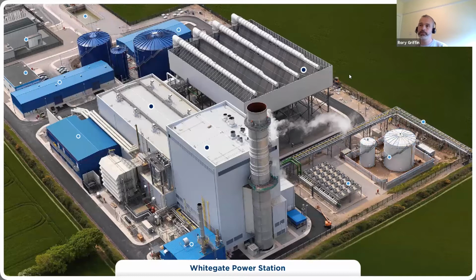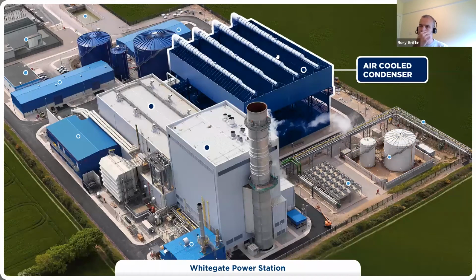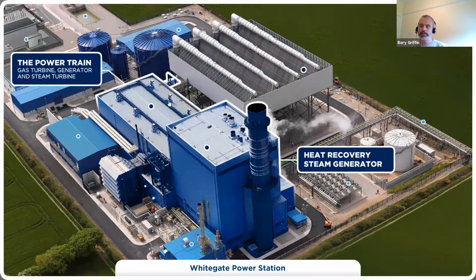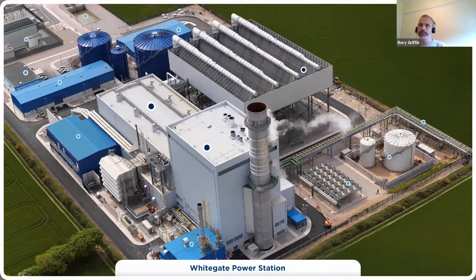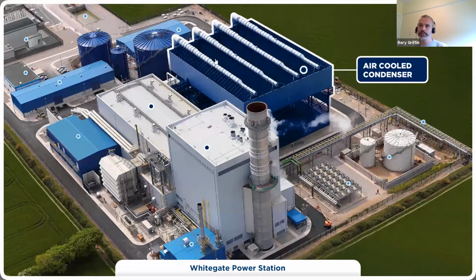And finally, just this structure here, this is the air-cooled condenser. So we'll go through the water cycle, but when you pass through the steam turbine and the steam needs to return back to condensate or water, this is used to basically condense it. We are close to the harbour, but from Whitegate village up to the site, you climb about 38 metres. And during the construction planning phase, the cost to put a pumping station down at the shore to pump up cooling water versus the efficiency gain, it wasn't worth it.